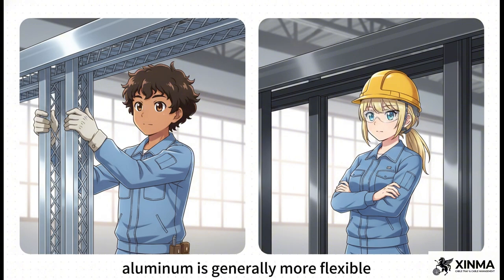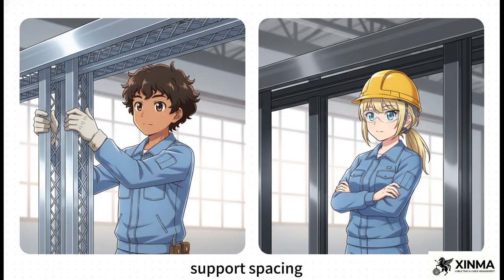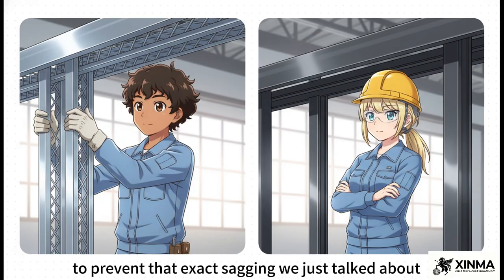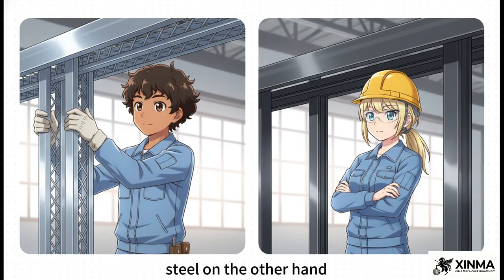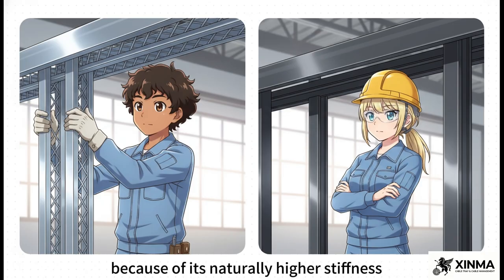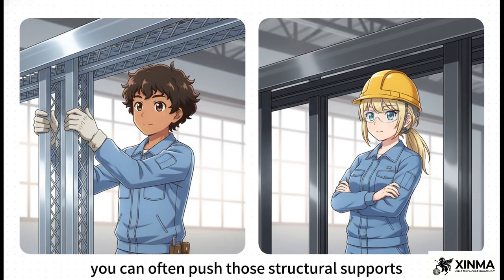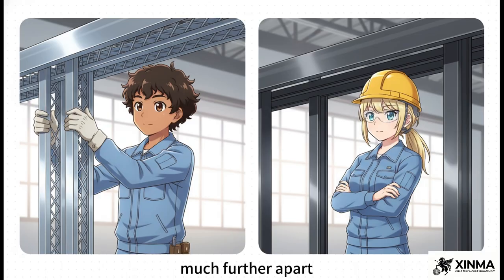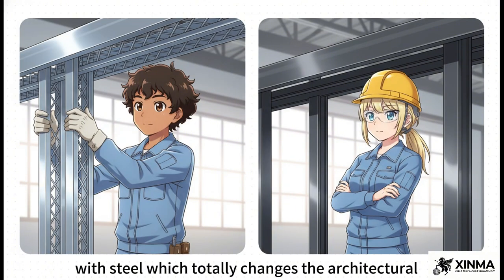Aluminum is generally more flexible, so what does that mean? It requires very specific, often much closer support spacing to prevent that exact sagging we just talked about. Steel, on the other hand, gives you a completely different span selection because of its naturally higher stiffness. You can often push those structural supports much further apart with steel, which totally changes the architectural and structural layout of the entire project.